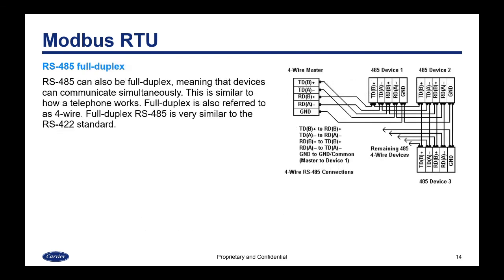RS-485 can also be full duplex, meaning that devices can communicate simultaneously. This is similar to how a telephone works, where two parties can talk at the same time. Full duplex is also referred to as four wire. Full duplex RS-485 is very similar to the RS-422 standard, and the way it works is that the extra pair of wires allows simultaneous communication.